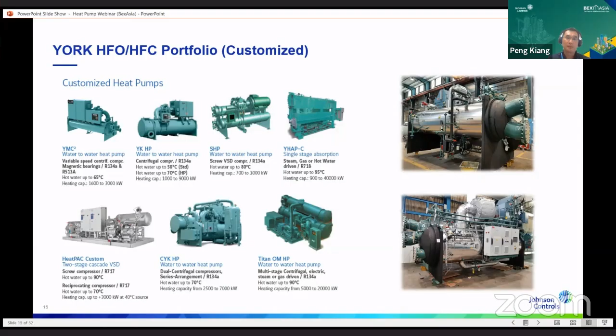And to be more sustainable in the future, as we are moving towards the direction of more sustainability, ammonia heat pump is also a very classic example of how we can use heat pump to generate hot waters up to about 90 to 95 degrees C, right? And it can cater for very large water delta T on the hot water side, from maybe like 30 degrees to about 90 degrees. So that's a very useful application of a heat pump in this case. So with our HeatPAC product, using natural refrigerant, ammonia, we can preheat waters to about 90, 95, and we can also pre-cool waters or do heat recovery.